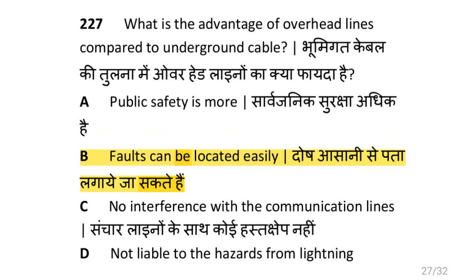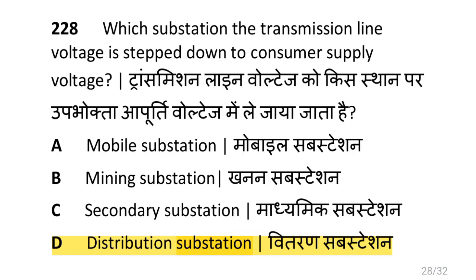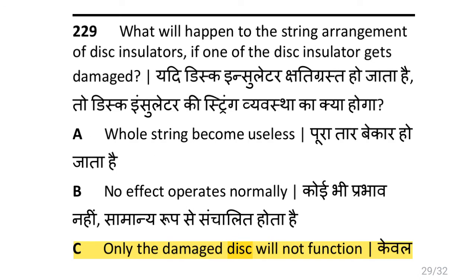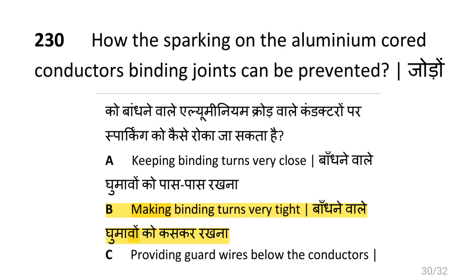What is the advantage of overhead lines compared to underground cables? That is faults can be located easily. Which substation steps down the transmission line voltage to consumer supply voltage? That is distribution substation. What will happen to the string arrangement of disc insulator if one gets damaged? That is only the damaged disc will not function. How can sparking on aluminum conductor binding joints be prevented? By making binding turns very tight.